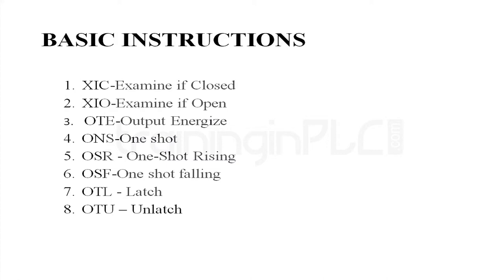So if you are using a normally open contact, and you are toggling it on, it will give a continuous pulse to the output, right? So whenever you are turning on the normally open contact, it will give a continuous pulse, so that your output will remain on until you turn off the normally open contact. But if you are using one shot in between your normally open contact and output, it will give exactly one pulse, right? I'll show you in the software.